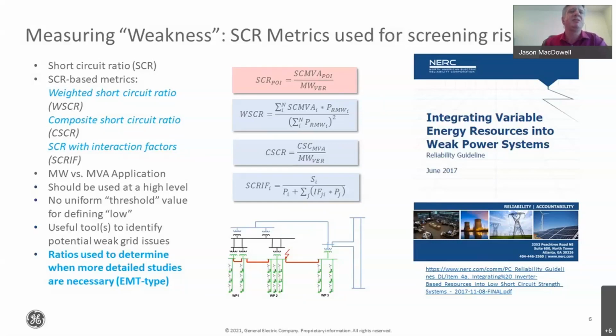But when you really need to look at the interaction of an area with many plants, looking at the composite ratio or weighted short circuit ratio, as we see there, is a better metric. It looks at the overall capability of the short circuit strength coming from non-inverter-based resources being fed into a particular point, relative to either the power being injected into the grid by inverter-based resources or the base capacity of inverter-based resources, as you see in the composite ratio.